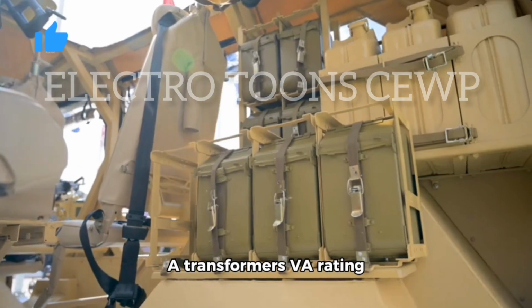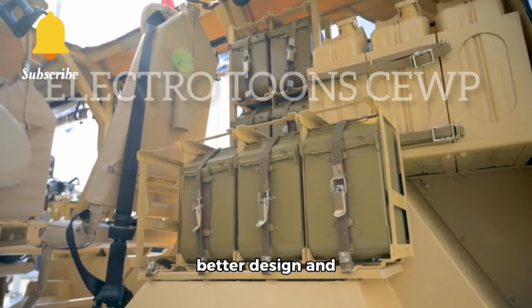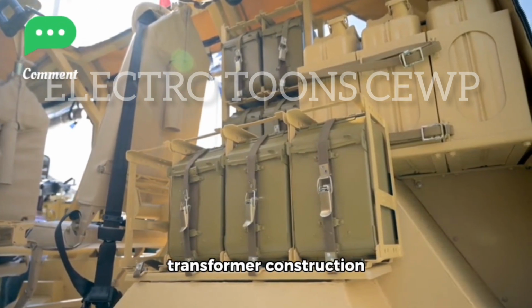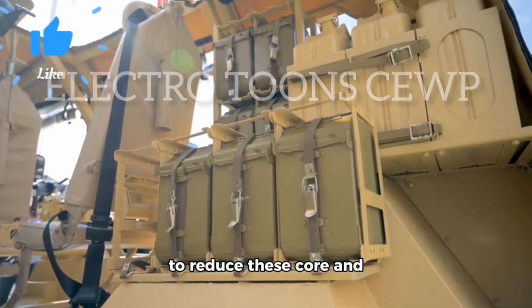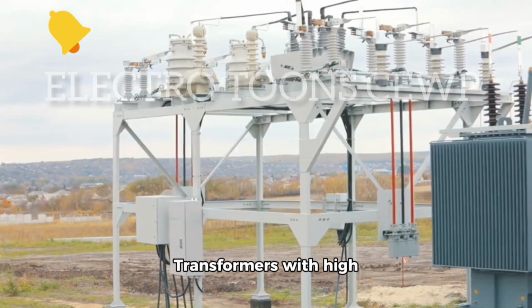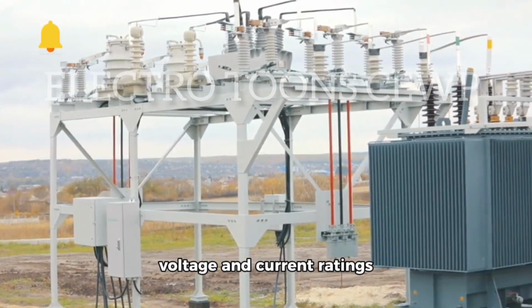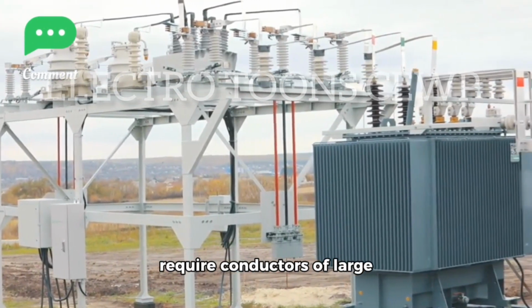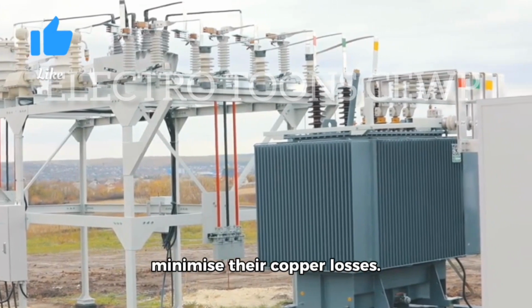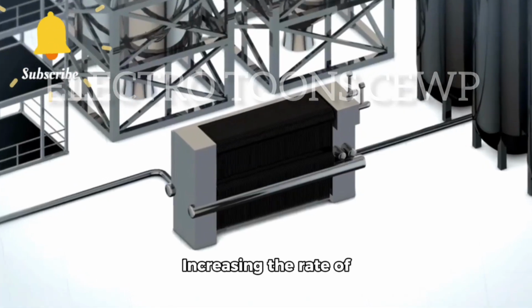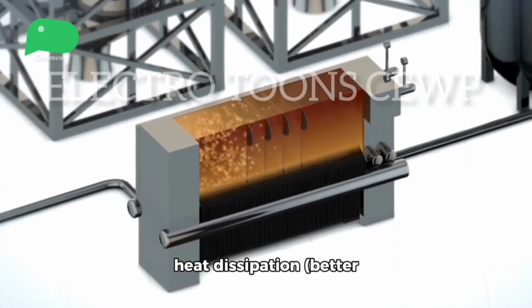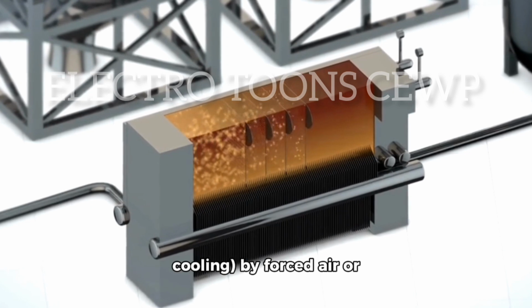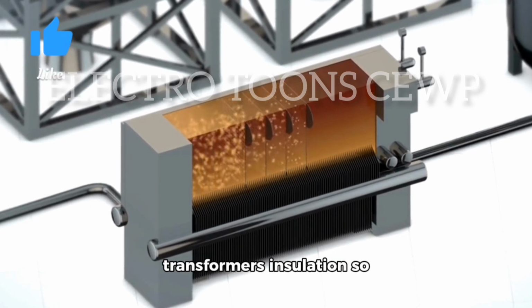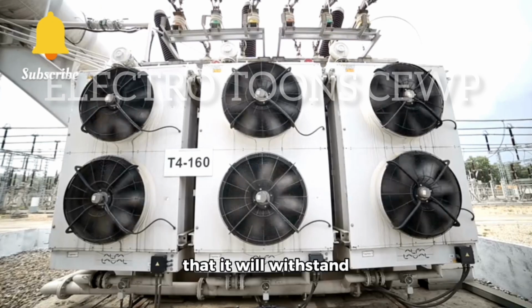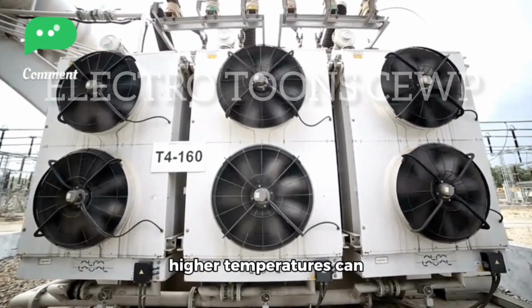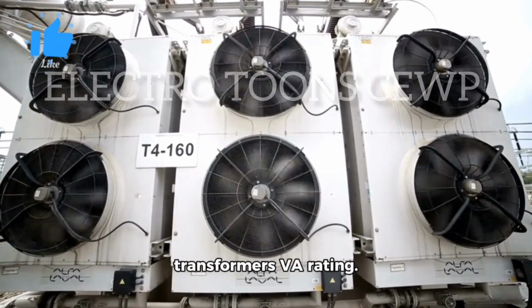A transformer's VA rating can be increased by better design and transformer construction to reduce these core and copper losses. Transformers with high voltage and current ratings require conductors of large cross-section to help minimize their copper losses. Increasing the rate of heat dissipation, better cooling by forced air or oil, or improving the transformer's insulation so that it will withstand higher temperatures can also increase a transformer's VA rating.